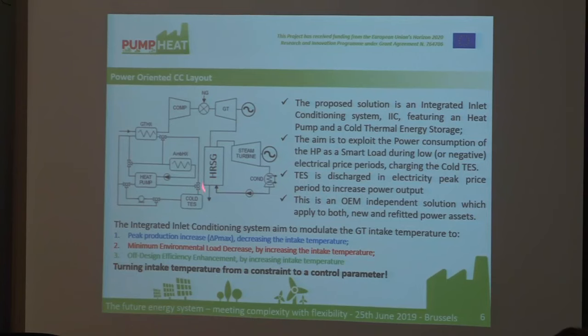The main idea is to have a heat exchanger in front of the gas turbine. Thanks to the combined cycle layout, changing the temperature in front of the compressor affects power much more than efficiency. So we get a kind of flat efficiency even while running at higher intake temperature, which lets us enhance efficiency while running off design. The main aim of this system is to increase peak production by decreasing intake temperature, to reduce the minimum environmental load by increasing intake temperature, and to enhance off-design efficiency by increasing intake temperature.